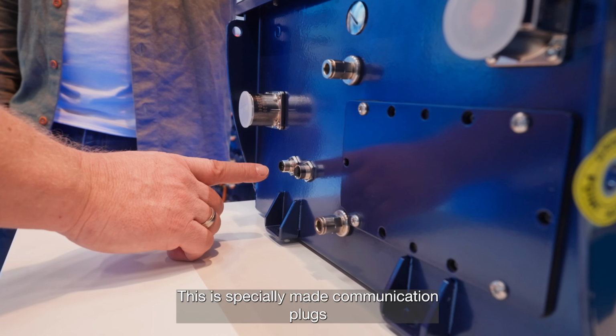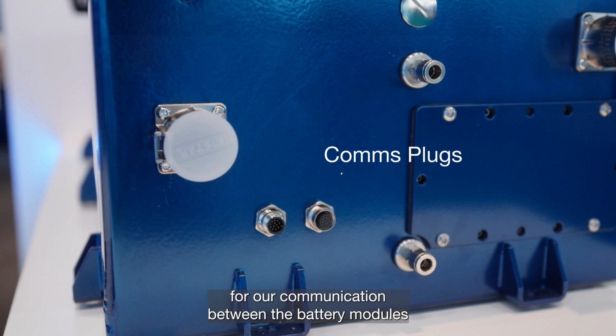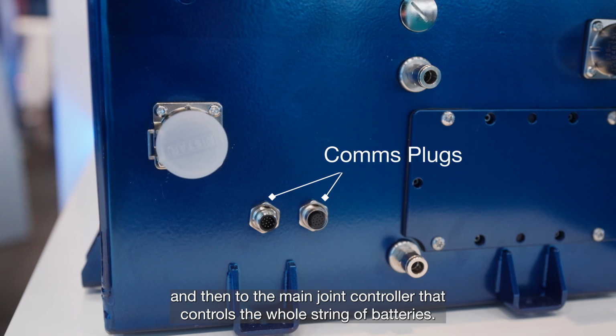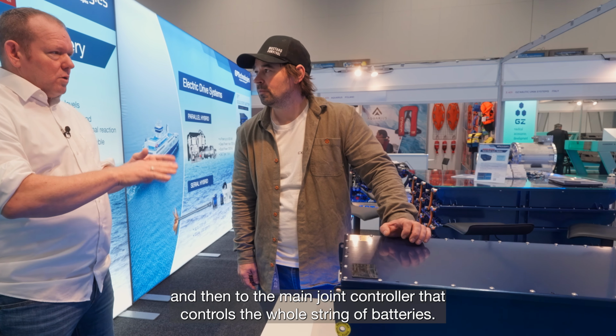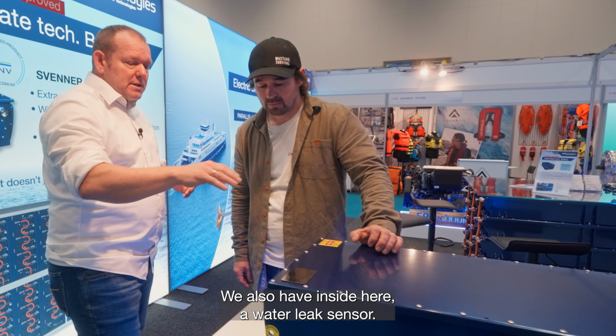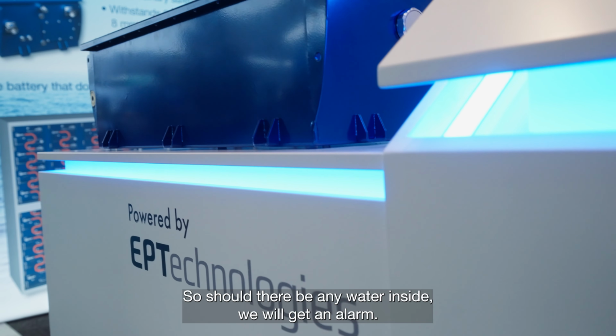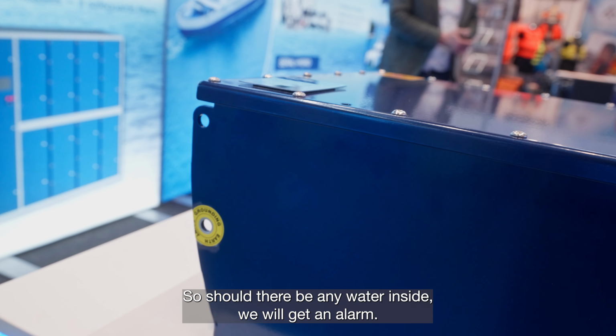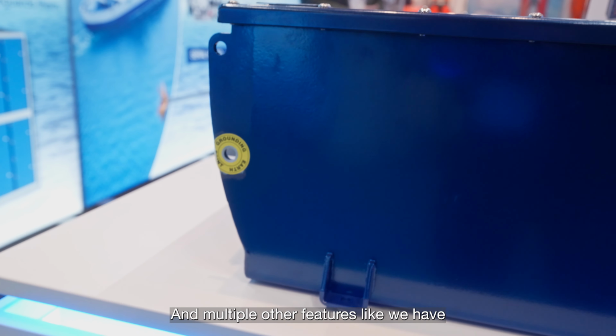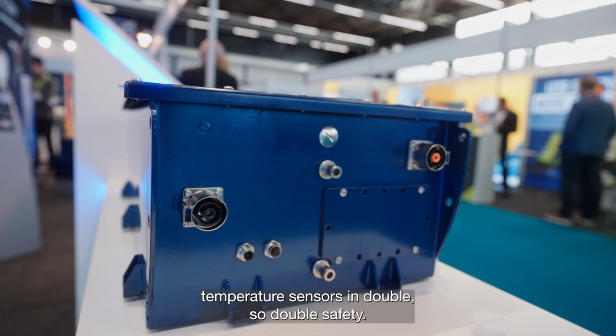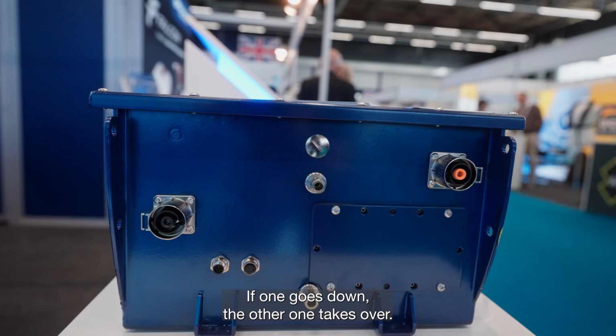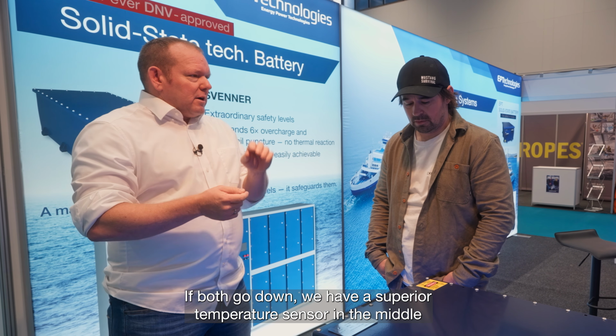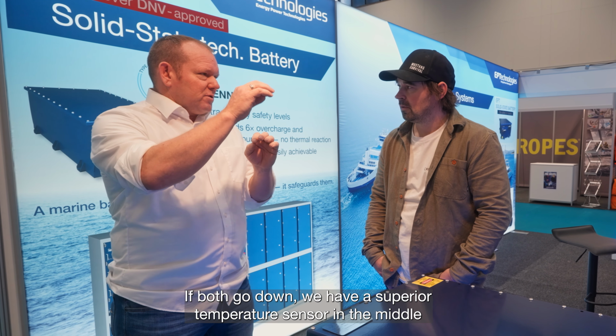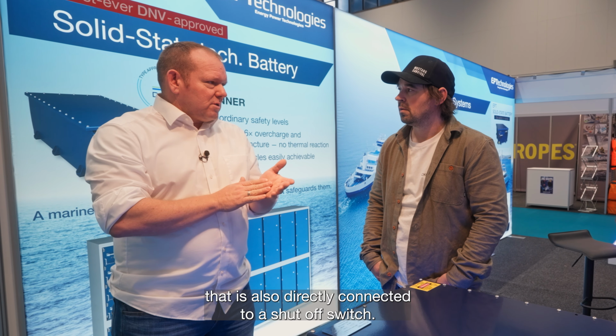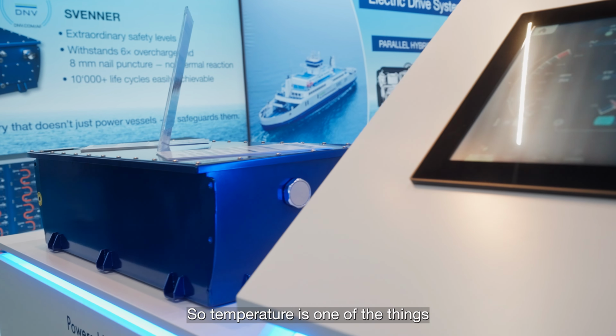These are special made communication plugs for communication between the battery modules and the main string controller that controls the whole string of batteries. We also have inside a water leak sensor, so should there be any water inside we get an alarm, and multiple other features, like temperature sensors in double, so double safety - if one goes down, the other takes over. If both go down, we have a superior temperature sensor in the middle that's directly connected to a shut-off switch. Temperature is one of the critical things here.